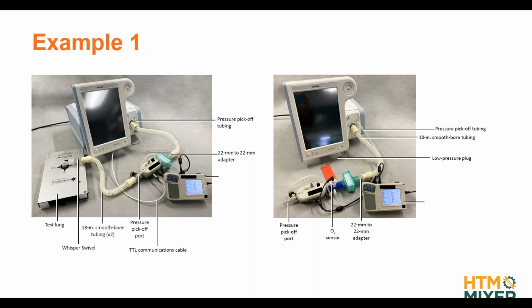These are two measurement setups from a service manual of a ventilator. You can see they're actually quite good pictures. So they did a good job in explaining the setup here, even though, if you look very closely, there is a teed-in pressure line here, which is very hard to see if you don't know that, but it is important because otherwise this specific model of gas flow analyzer is not going to compensate for the pressure in your flow measurement.